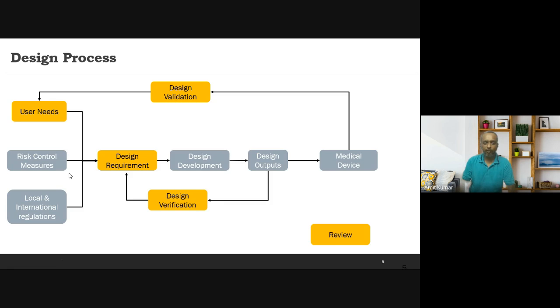Risk controls, how do they play a role? What we try to assess is, if something goes wrong, what would it cause? What if it causes harm? In certain situations it becomes a hazardous situation and a harm. That is all controlled and documented here, as risk control measures. It is important to do this activity so that we don't miss out the safety part of it. So here, what the user wants, this is the safety part, and this is what regulation wants.